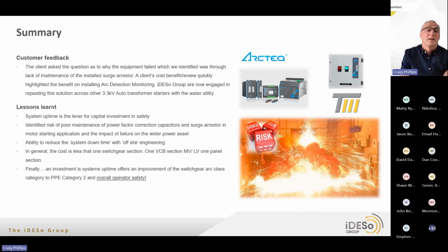The customer's feedback was very much wanted to understand why the system had failed. We advised them of the surge arrestor failure. Client took time to investigate themselves, and a quick cost-benefit review highlighted the benefit of installing arc detection monitoring for protection of equipment. And now, as an organisation, we are working ongoing with this client on other 3.3 kV auto transformer motor starters to remove this particular risk.